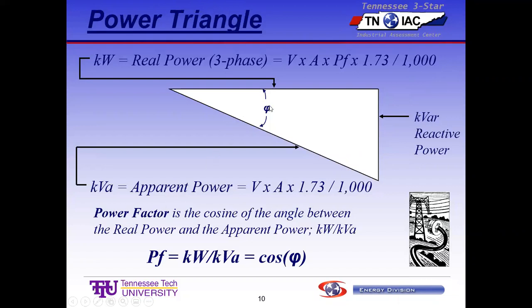So as the power factor gets worse, this reactive power side gets longer and longer, which makes the hypotenuse get longer and longer, but the kW side doesn't change. And when this side gets longer, the only way the hypotenuse can get longer, since the voltage is constant at whatever it is (square root of 3 is constant, 1,000 is constant), is that the amps have to go up. So that's kind of the effect.